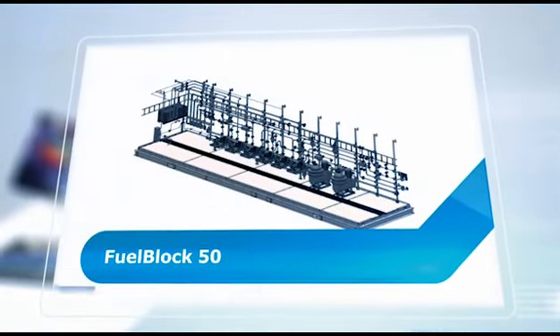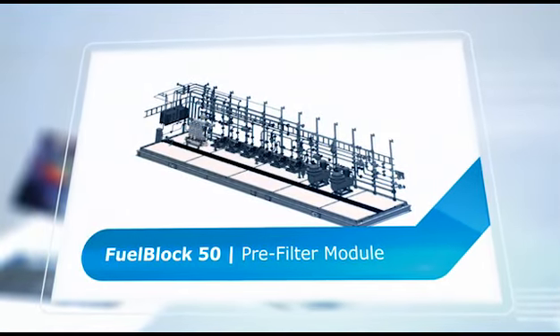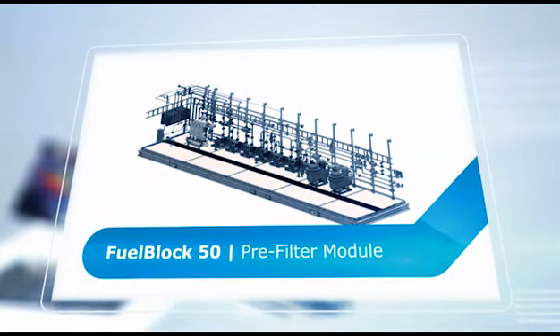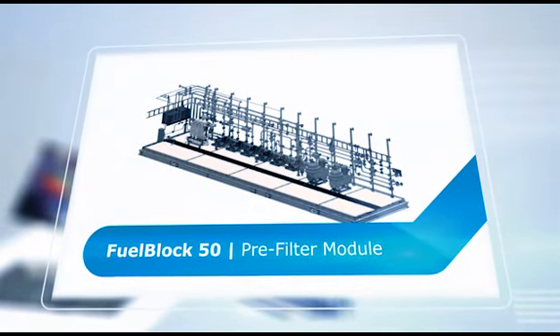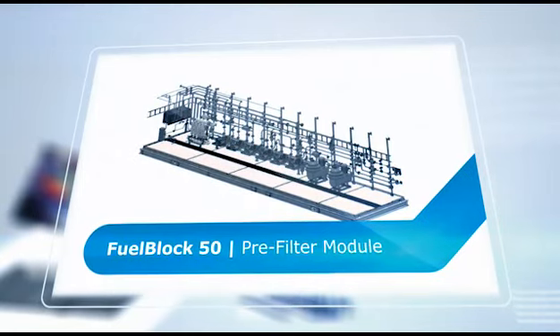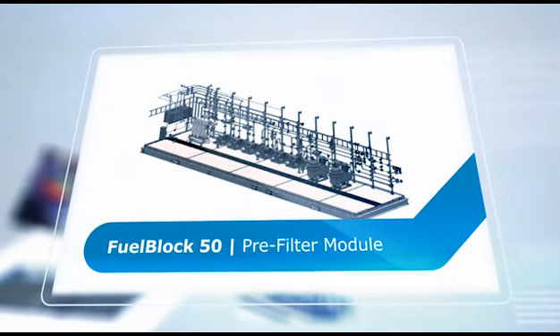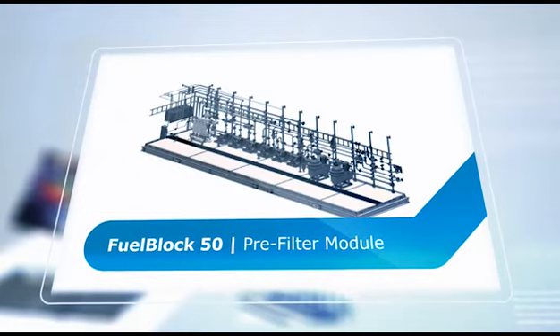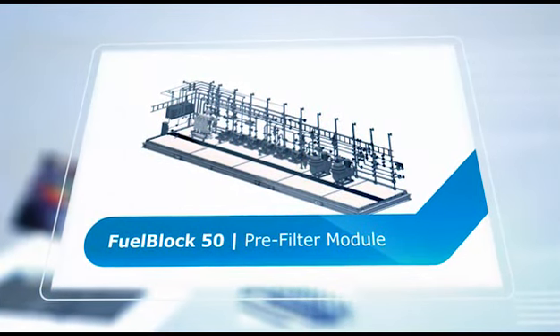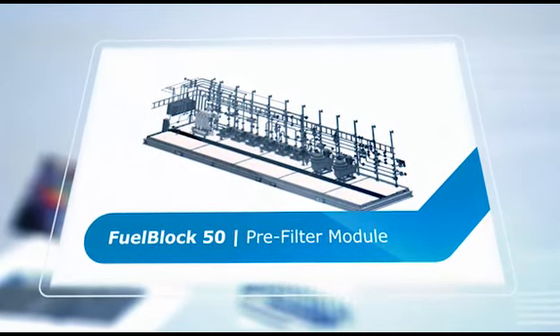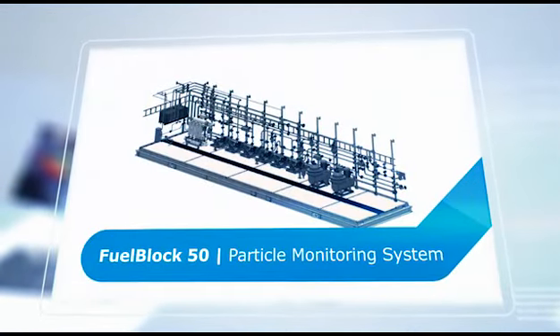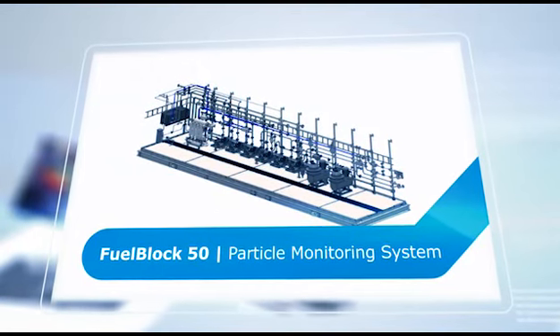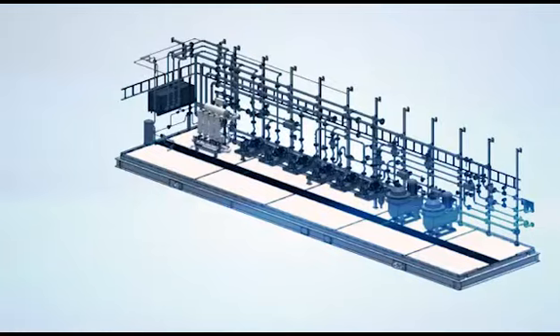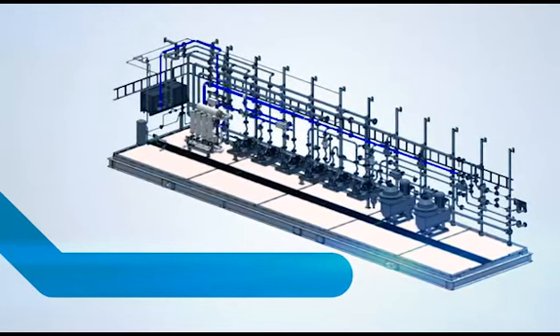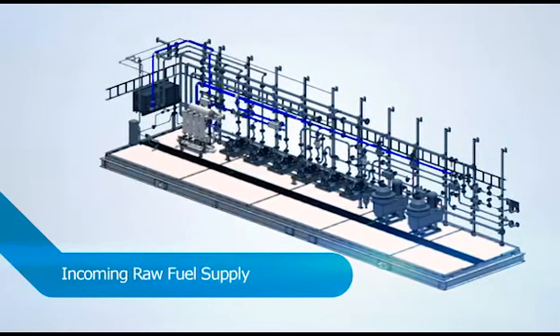A pre-filter module is available for initial filtration of raw fuel received from tankers or bulk suppliers. The filter employs surface-style elements that automatically back flush when required. Incoming raw fuel can be paused during a back flush or allowed to continue unfiltered to the raw fuel tank. Fuel particle analyzers can be supplied to provide ISO 4406 code sample data and long-term trending of fuel particulate levels of the incoming raw fuel supply.